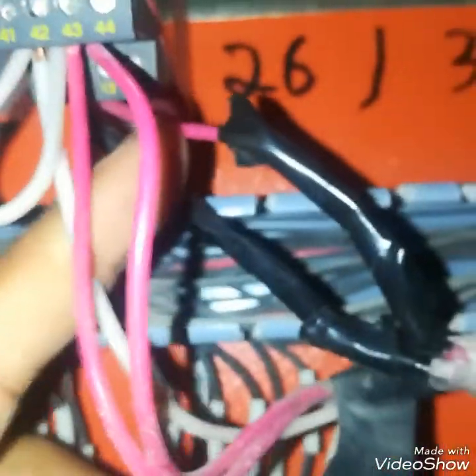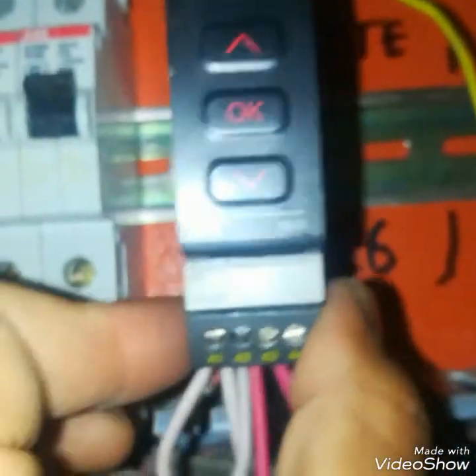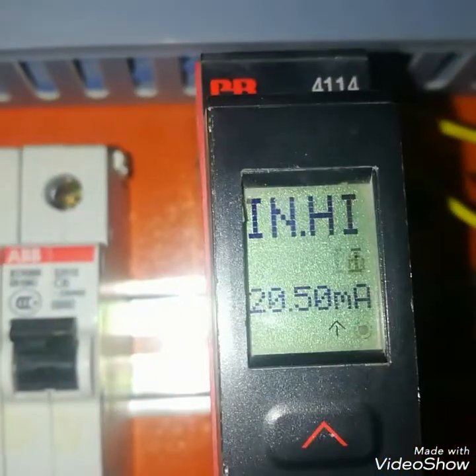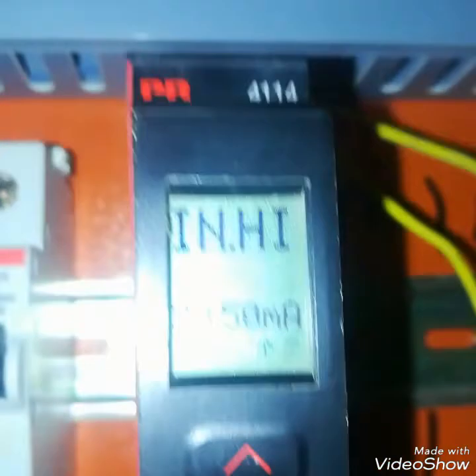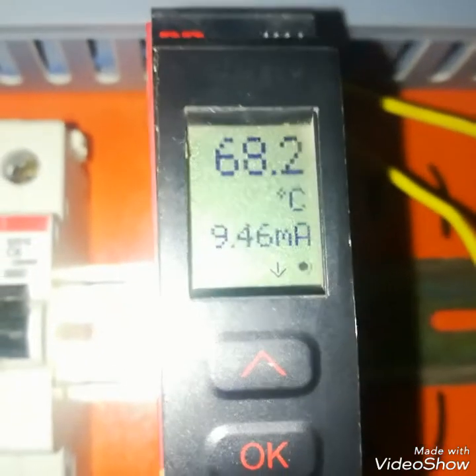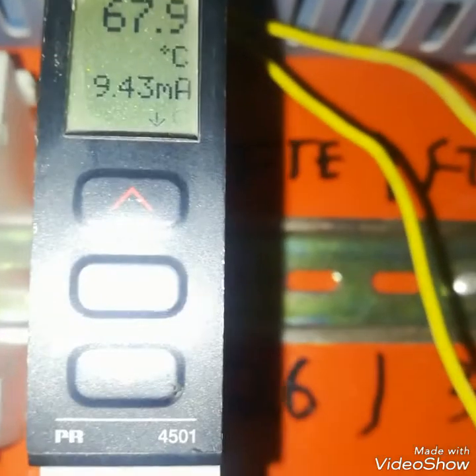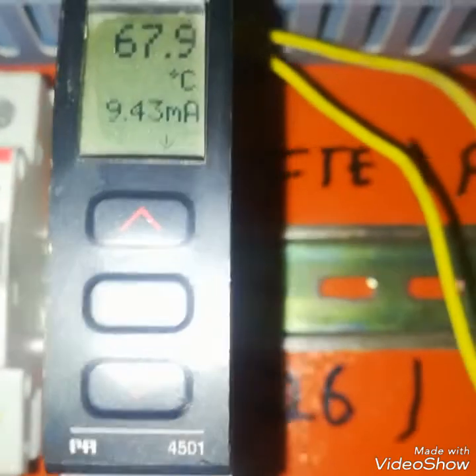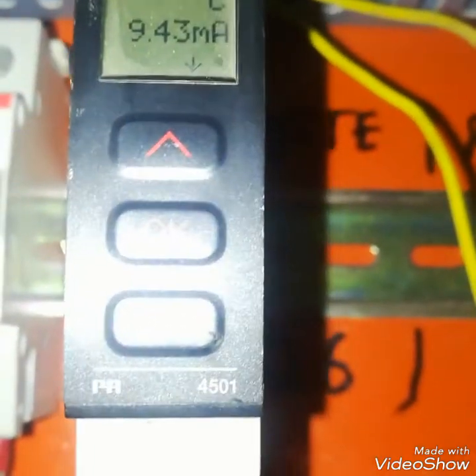This is the analog output, and this is the input RTD. When I remove this jack, this transmitter will show an alarm. I am removing it just to show you. This is the RTD. It is showing high in, that is input is over range, because PT100 is open now, so the transmitter is giving an alarm. So these were the parameters and connections of this PR transmitter. I just showed you the PR4114.